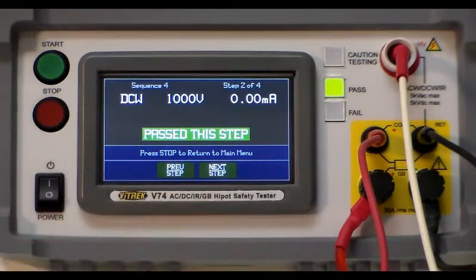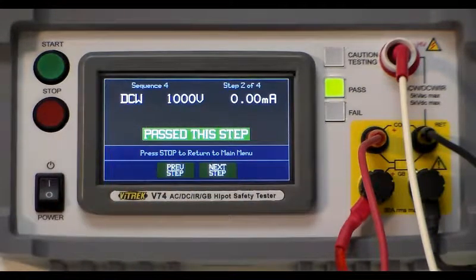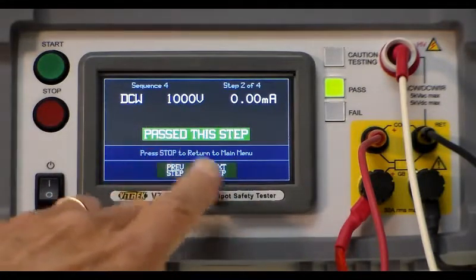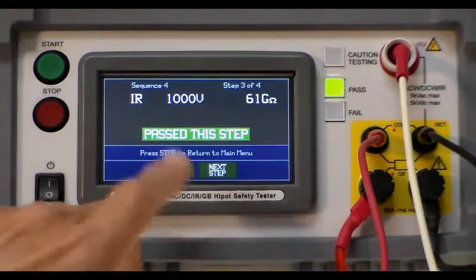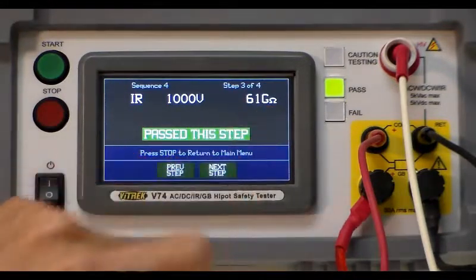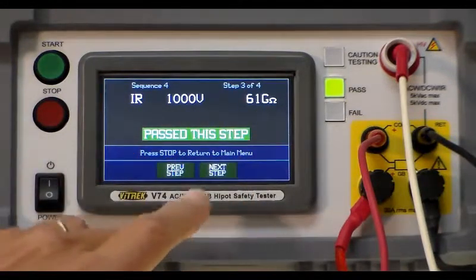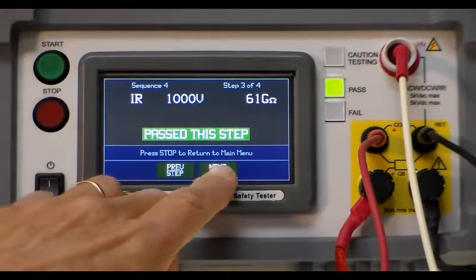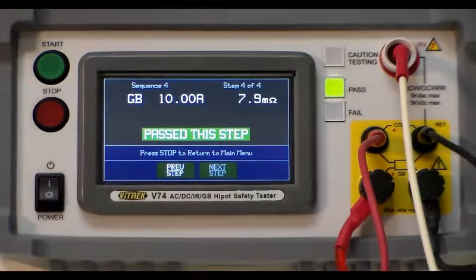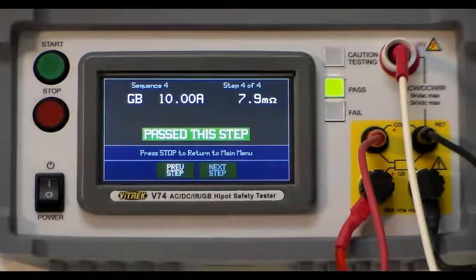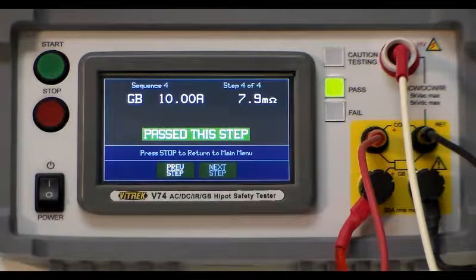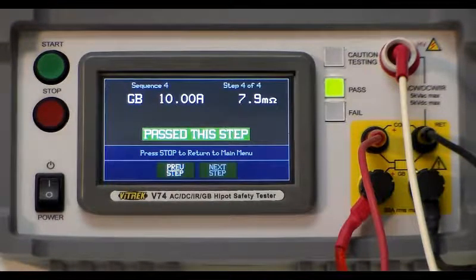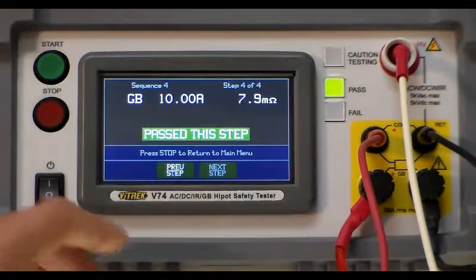The next step would be DCW which gives you a zero. The next step is the IR. It gave a 61 giga ohms as a reading. The next step would be the ground bond and it was 7.9 milli ohms so it passed all these tests.